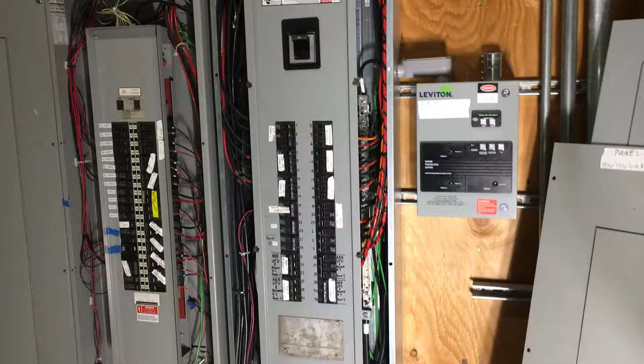There's been electrical modifications done by the contractor here. This system had been running for several years, incident free, nothing wrong electrically. Then once this contractor started modifying electrical, adding panels, putting in lights, I kept getting called out to nuisance calls for error 53, which usually means communication loss, usually when it's losing power, and that's what it turned out to be. Switches were hit, circuit breakers were hit. Then it started blowing out fuses on air handlers, and I said there's gotta be an electrical problem.